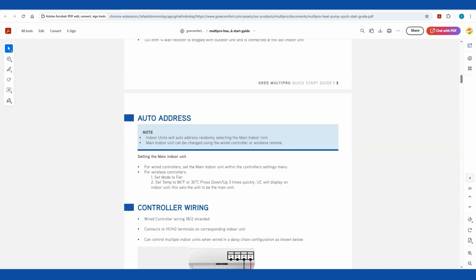Make sure the homeowner or end user also knows that when you switch modes, like you go from wintertime and heating to cooling, make sure you go back to each one of those rooms and make sure the set point's where you want it to be, because whatever your set point was in heating, if you only change it on the main indoor unit, that's the set point that's going to be held in cooling mode now.